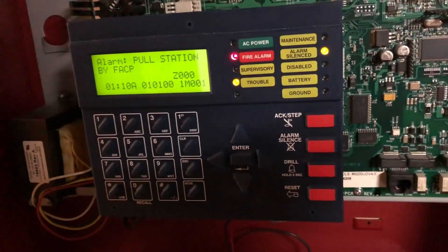It's unfortunate that Fire-Lite, for whatever reason, did not design their system to have filtered DC — I can complain about that for days. But I hear the new ES series panels have fixed that, and now all have filtered DC, which is very nice. But that's a topic for another day. This panel — if I hit one pull station here, then go hit another pull station that's also on zone zero, for whatever reason that doesn't cause it to go into second stage.